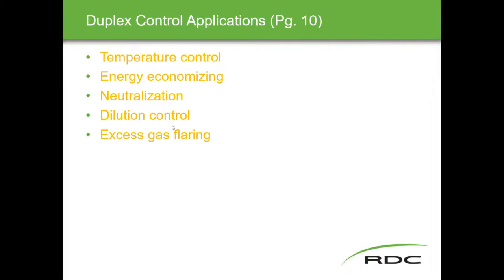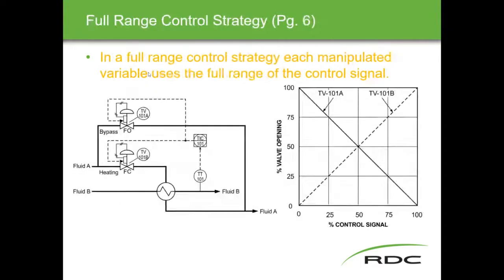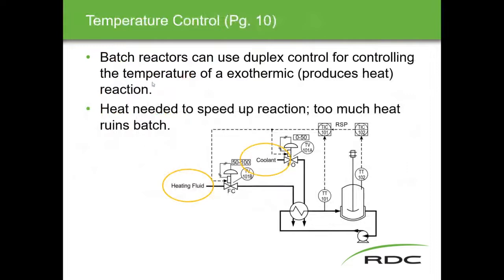All items in orange tie to self-test questions. Looking at temperature control first: a batch reactor example where we're mixing materials in a tank and require heat to drive the reaction. Too much heat ruins the reaction, so batch reactors are a good example of a temperature control scheme using duplex control to simultaneously control the flow of coolant and the flow of heating fluid.